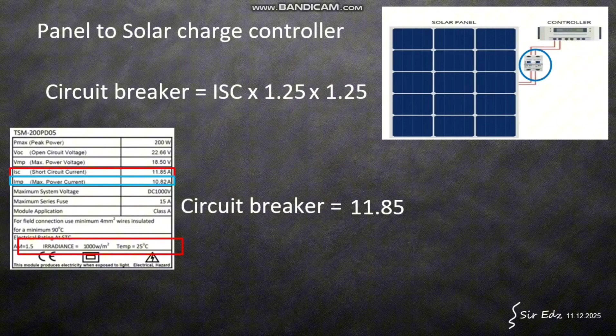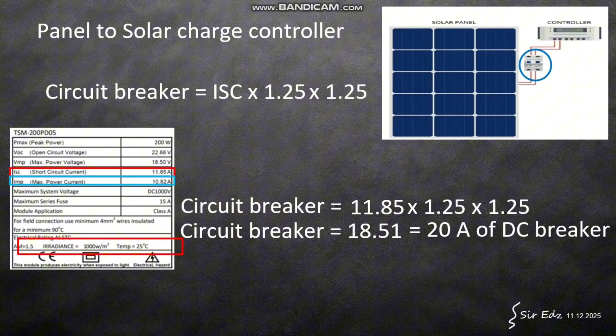So we multiply by the 1.25 safety factor and another 1.25 for solar irradiance, and we get around 18.51. Since there's no 18.51 ampere circuit breaker available in the market, we get the 20 ampere DC breaker.